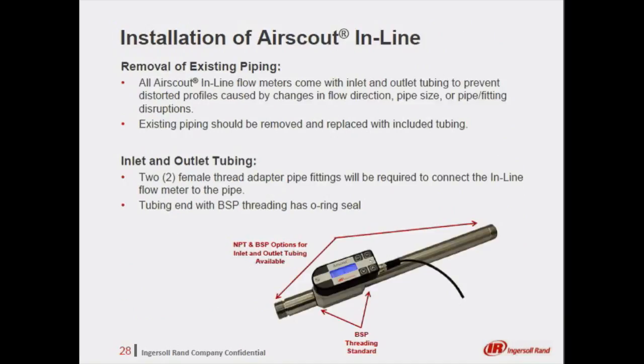When installing an inline flow meter, the existing piping should be removed and replaced with the inline flow meter's inlet and outlet tubing. The stainless steel tubing supplied with the flow meters offers a uniquely smooth transition to the inline fitting. Many times the connection of the inline fitting directly to the standard threaded pipe fitting causes the flow profile to be distorted, potentially affecting the readout results.